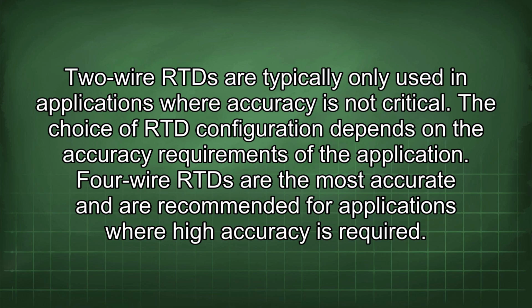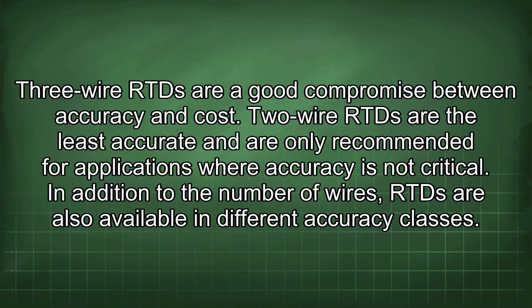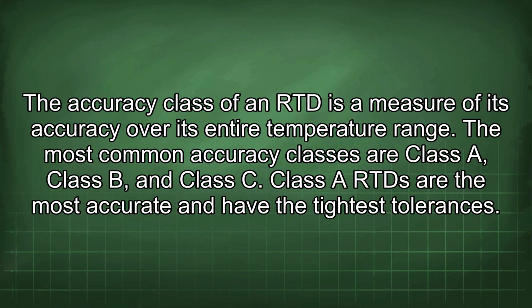The choice of RTD configuration depends on the accuracy requirements of the application. 4-wire RTD are the most accurate and are recommended for applications where high accuracy is required. 3-wire RTD are a good compromise between accuracy and cost. 2-wire RTD are the least accurate and are only recommended for applications where accuracy is not critical. In addition to the number of wires, RTD are also available in different accuracy classes. The accuracy class of an RTD is a measure of its accuracy over its entire temperature range.